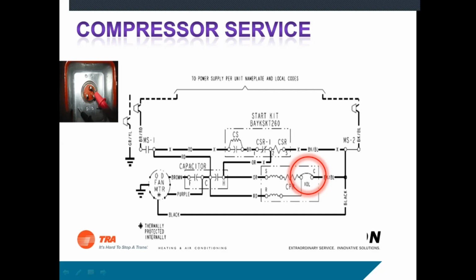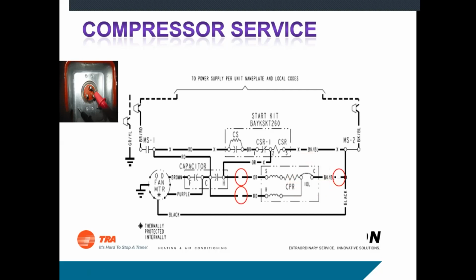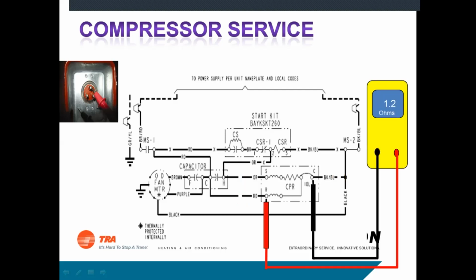So if you want to do some ohm readings with the wires connected, just make sure that somewhere you disconnect the wires from the system. So if you pull the plug out or disconnect them at the contactor, that's fine. But make sure that this is an isolated circuit if you're looking at the wiring schematic before you start doing ohm readings, because you're going to get backfeed. If you leave the wires connected and you start doing ohm readings, you're going to get backfeed through these circuits and these contactors and different things. So anyway, pull the wire plug, and then we can take some ohm value readings.